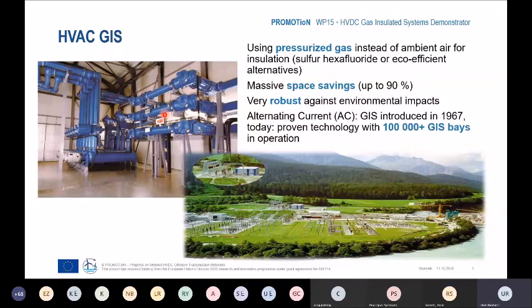There are a lot of advantages if you compare this gas insulated technology with the air insulated technology. You can also have a look at the other picture, where you can see an air insulated switchgear and the same switchgear using gas insulated technology. The main advantage of gas insulated switchgear is the massive space saving. We can say up to 90% space saving compared to air insulated technology. Another advantage is the robustness against environmental impacts. These two advantages make gas insulated switchgear favorable, especially for offshore applications, where space is one of the most important requirements.